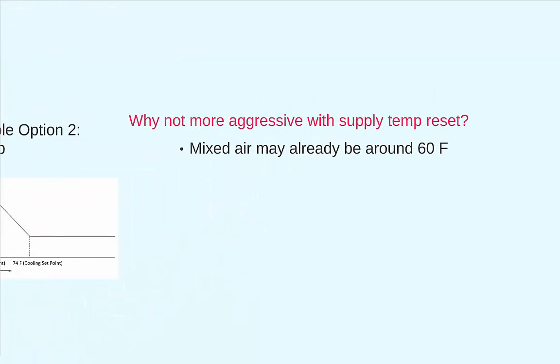That is, we didn't operate a chiller and chilled water pumps to bring the temperature down to 60 degrees Fahrenheit, and we didn't implement an economizer cycle to bring it down either. We simply ended up at this temperature for reasons out of our control, like adhering to code requirements to bring in the appropriate amount of ventilation air.